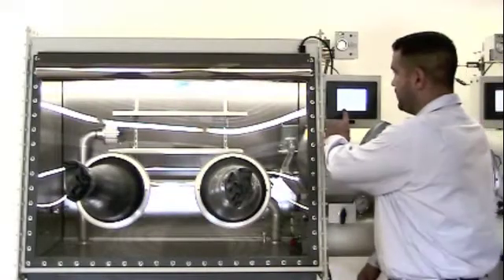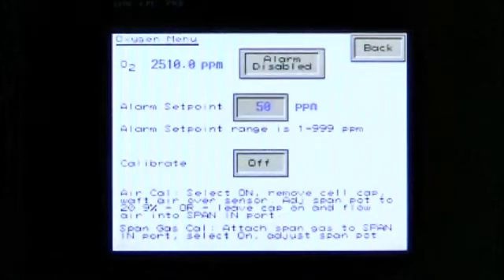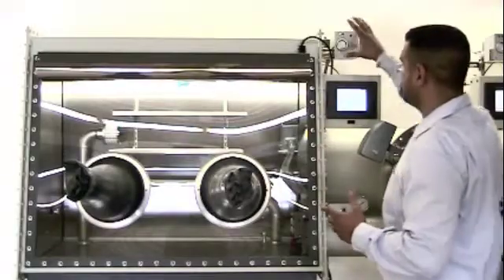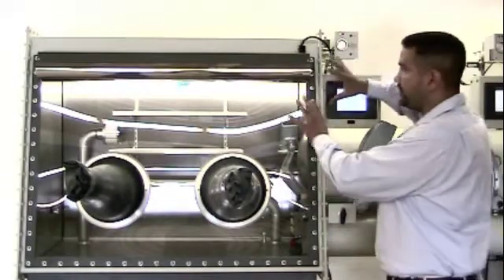To begin, enter the oxygen menu. From this menu, activate and enable the calibration routine. Enabling the calibration routine isolates the cell block from the glove box.